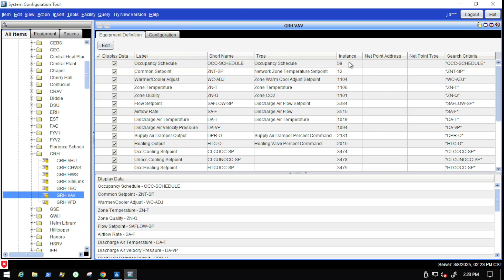Something else you need to be aware of as well when you are setting these up. This is basically search criteria. When you are looking for the particular points within your system, if you have this instance ID filled in, basically it's going to default to that instance ID. And if you ever get into a situation where you're seeing points that are mismatched as far as the location, like for example, you have an analog output or an analog input displaying where an occupancy command is or something like that, it is going to be because of this right here. If you've got multiple VAV types, different generations and things like that, this is why it's going to fail and default to that instance ID.